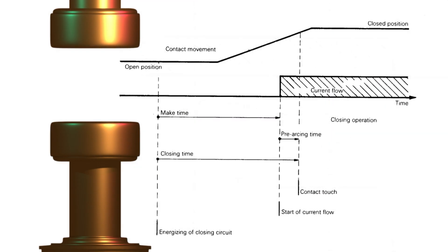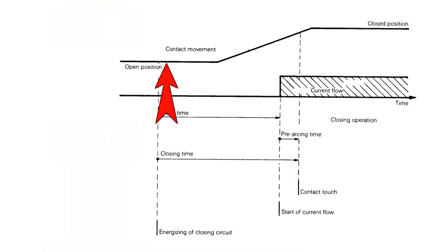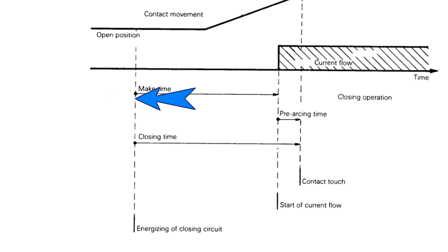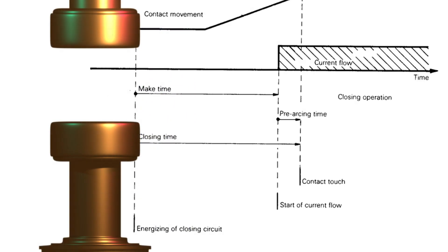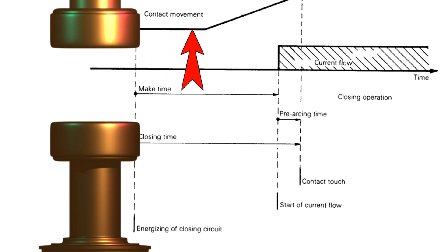Now we come to the closing time of a circuit breaker. This horizontal line represents the open position of the circuit breaker. At this moment, the closing circuit is energized. But even when the closing pulse reaches the closing coil, the circuit breaker does not begin its closing operation immediately — the moving contact does not start moving towards the fixed contact right away. This delay is due to the time taken for mechanical movement to propagate through different hinges, levers, and gears before reaching the moving contact. After a short delay, the moving contact begins to move towards the fixed contact.